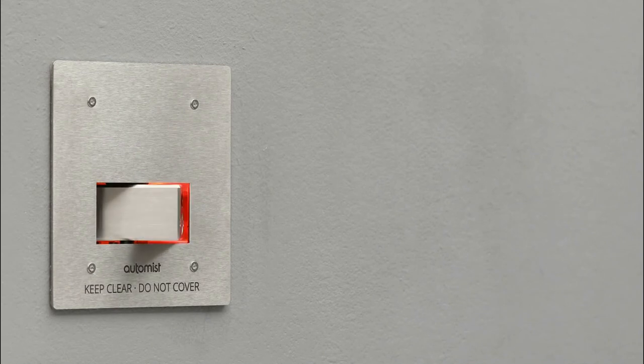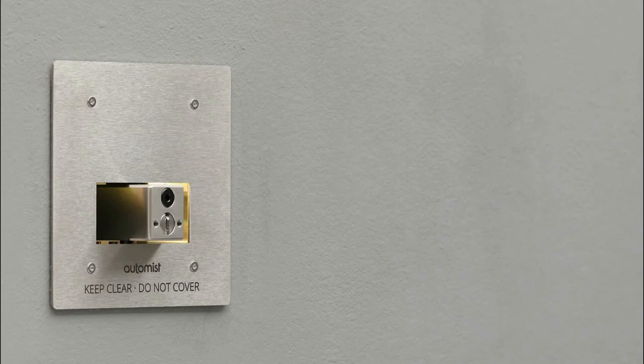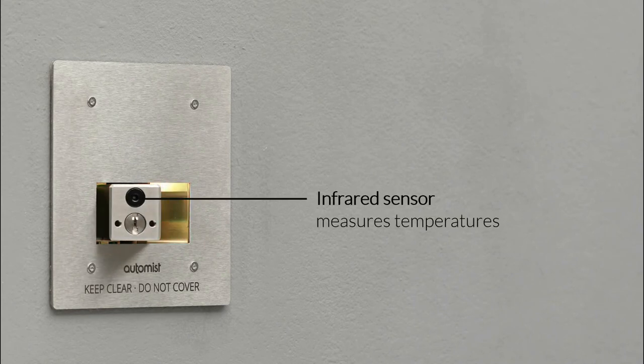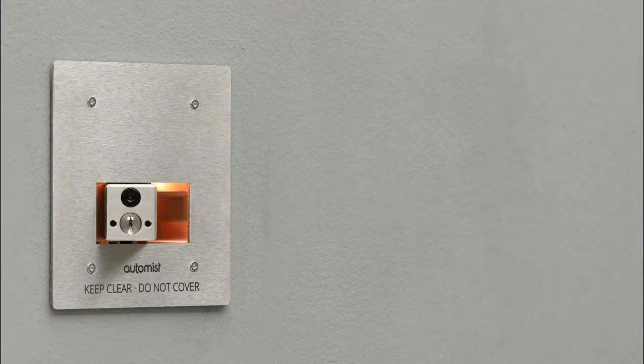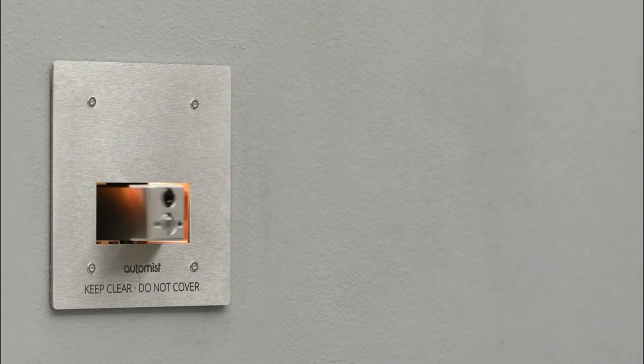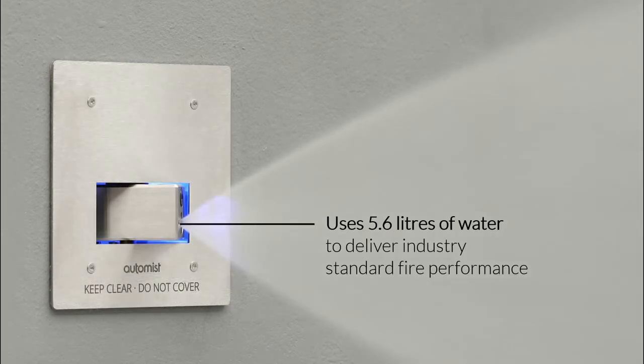So you can see it here, and what we're doing is we're building a thermal image of the protected space. And that's made possible by this infrared sensor mounted on the unit that measures the temperature. Once it has pinpointed the location of the fire, it locks on and then deploys a targeted blade of water mist. The system uses 5.6 liters of water, so less than a power shower, to deliver industry standard fire performance.